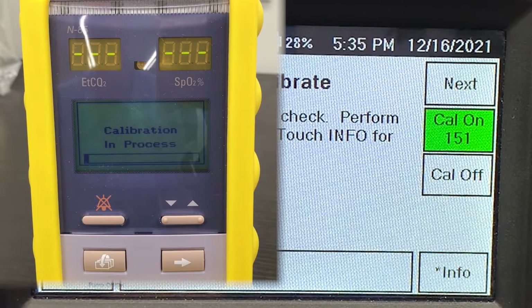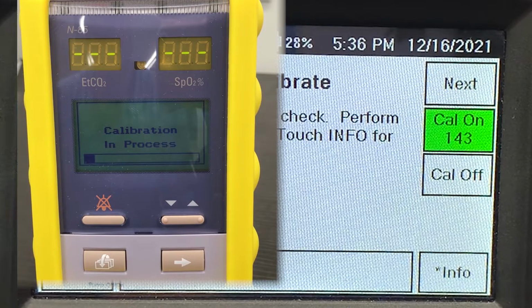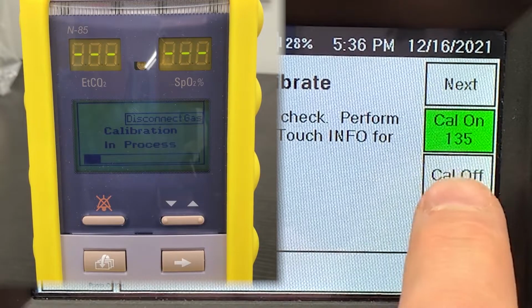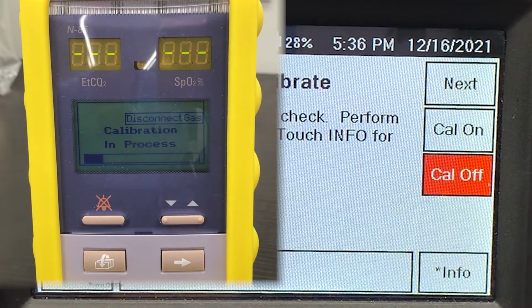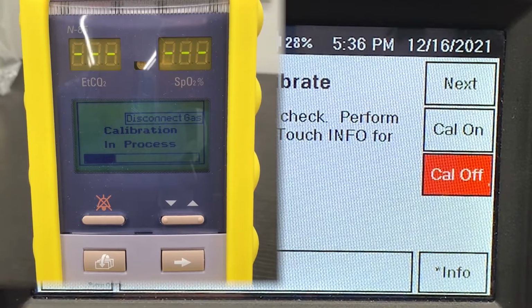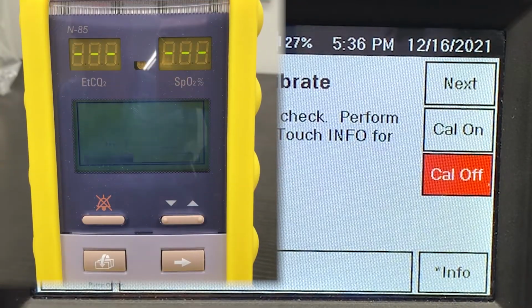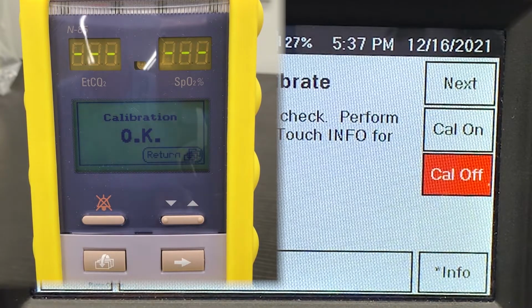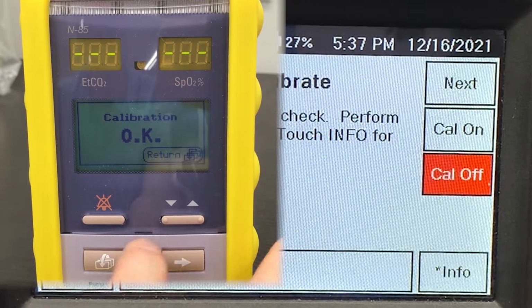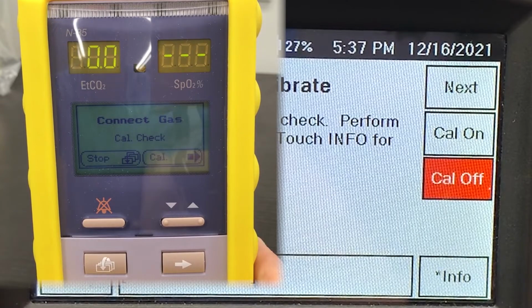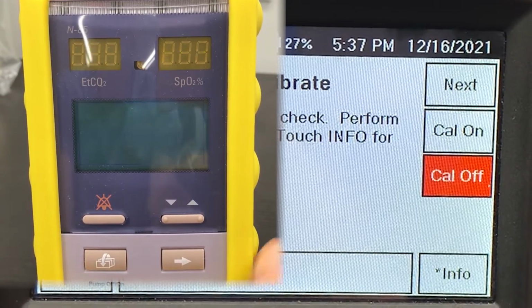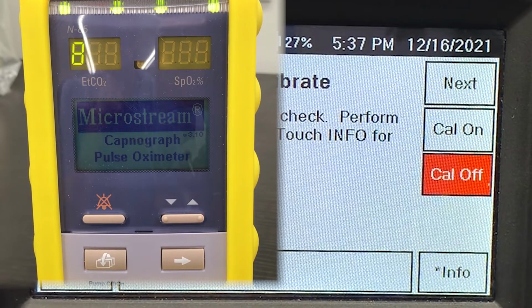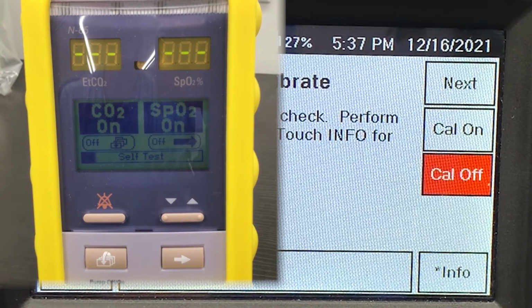Now we're going to watch the screen. It'll tell us to turn the gas off once it's collected enough data. So there it is, disconnect gas, and so we turn the cal gas off on the smart tank to conserve calibration gas. And then we just wait for the monitor to do its calculations and calibrate itself. Once the monitor says calibration okay, it's finished, and we can push this exit button. And again, the monitor essentially reboots and does its self-test again. Should be calibrated.